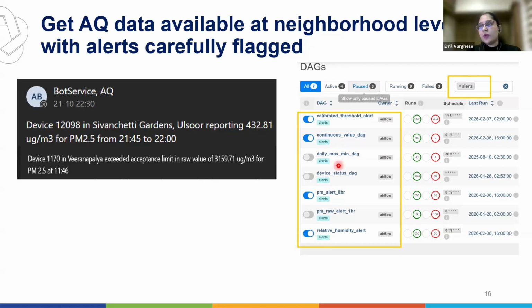Another thing to look at is if there's no change in the maximum and minimum values over a day. Say you have an RH sensor and the RH is not changing at all, while ideally it should change throughout the day — higher RH in the mornings, lower in the afternoon. If there's no change at all, you can pull that from this particular alert.